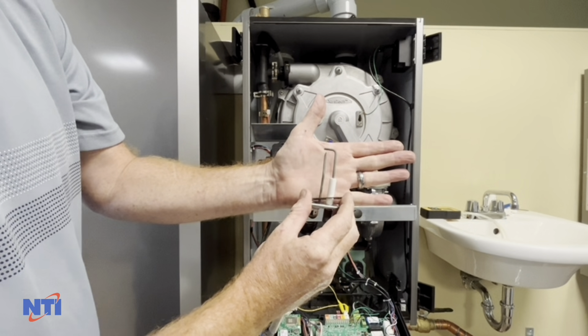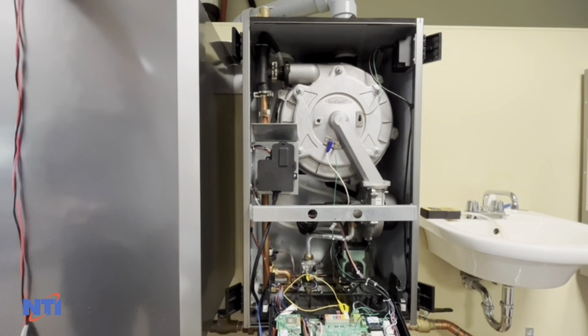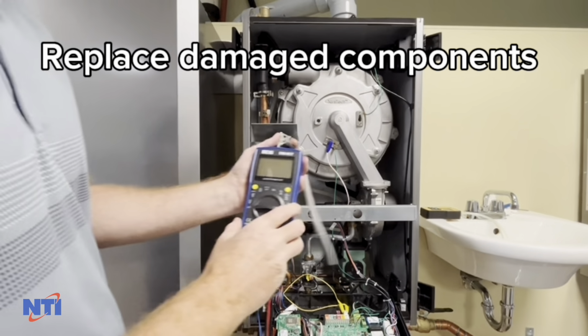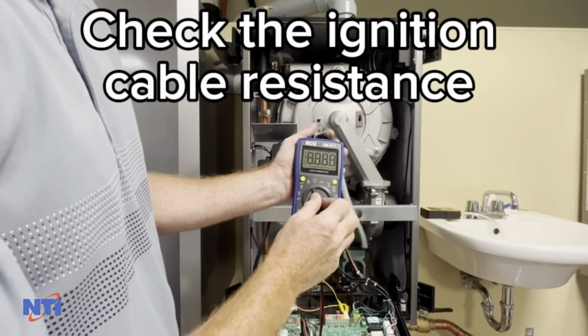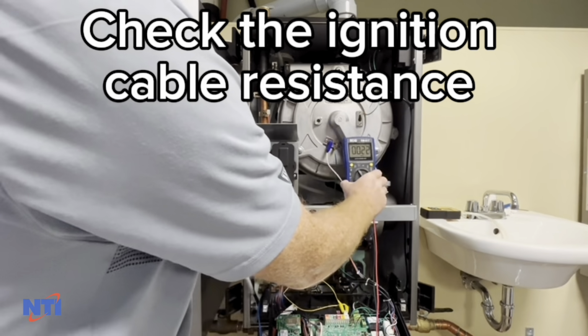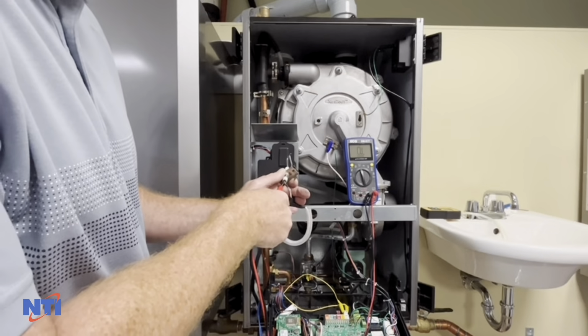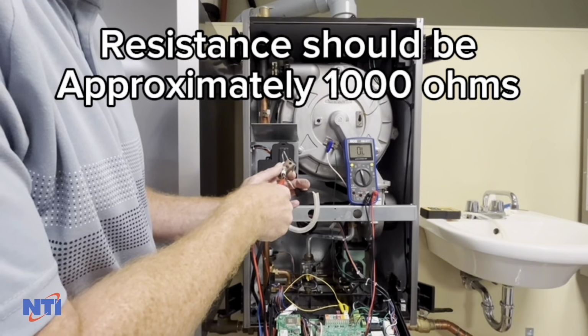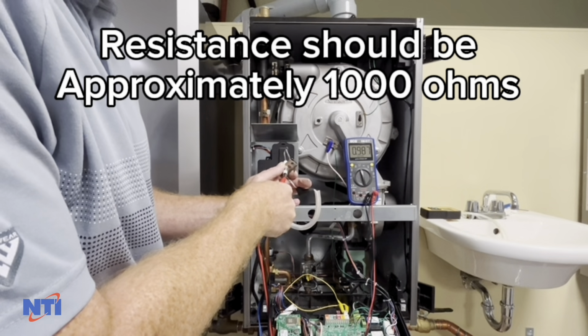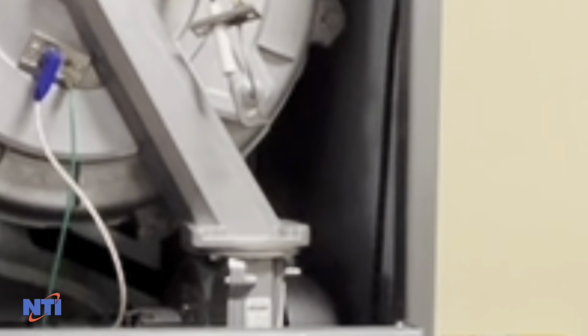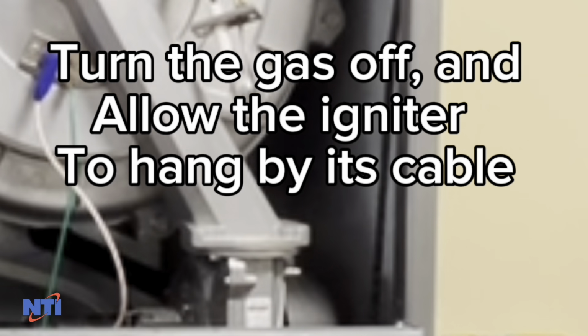The ignition cable and igniter are one assembly. Test them together by measuring resistance through the cable to the plug on the igniter. Resistance should be approximately 1000 ohms. Turn off the gas so the igniter can be tested. Remove the igniter, allow it to hang by its cable, then observe for a strong spark.